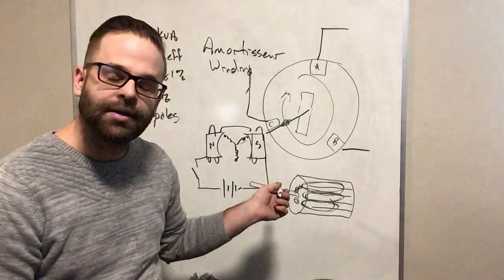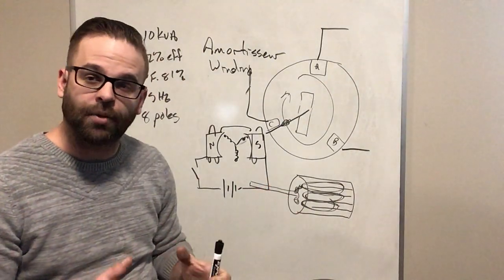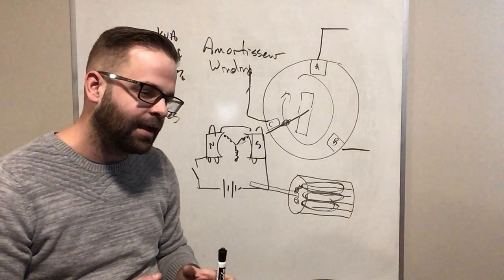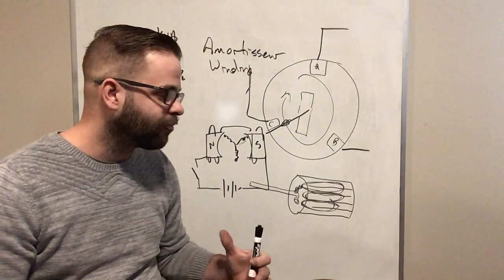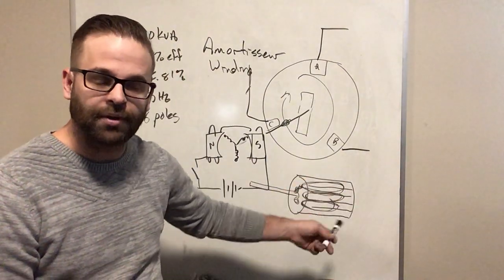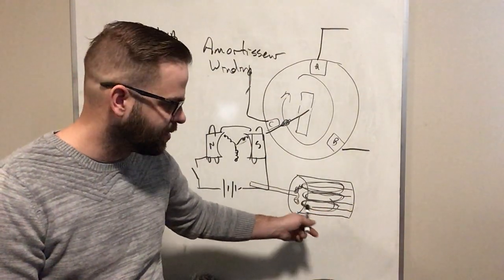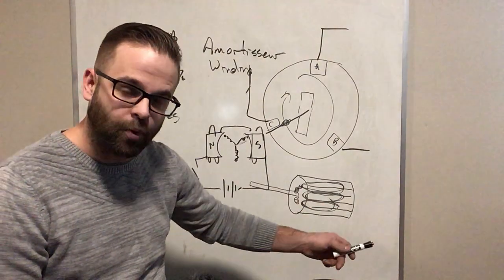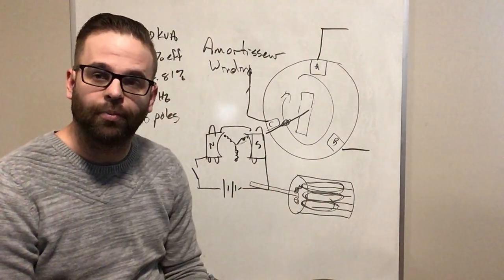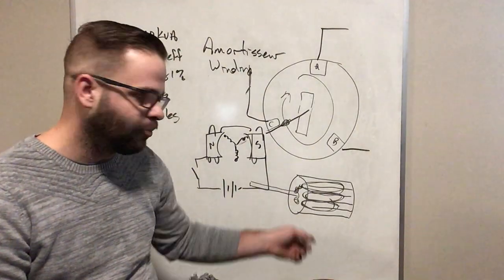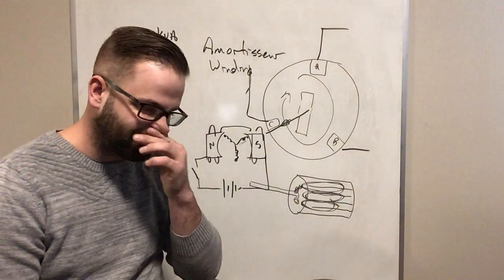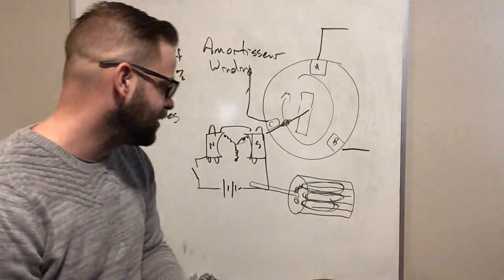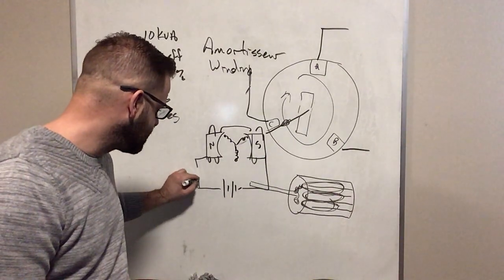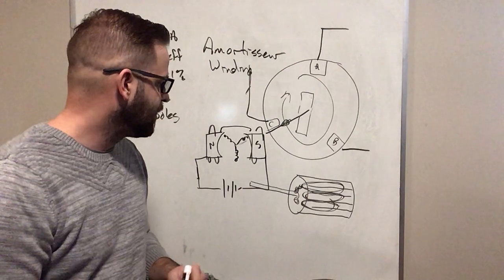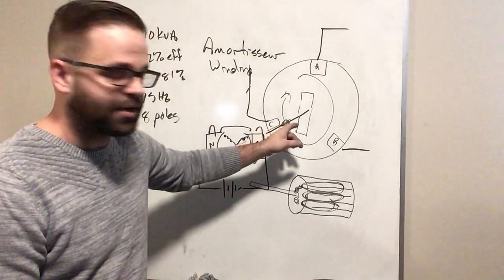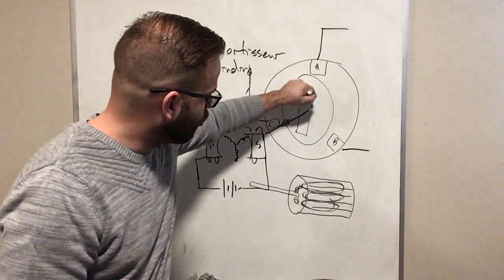Because what happens is the amortisseur winding is made of small copper, aluminum, or steel bars, and if I put it under load or leave it for a longer time, it's going to start heating up that amortisseur winding more and more, and what will end up happening is that amortisseur winding will burn out and then the motor will be screwed. So the amortisseur winding is only to get the motor up to speed. Once the motor is up to almost synchronous speed, we then close our DC excitation switch, and that ends up producing our three-phase voltage that gets rectified, comes out and gives me a north and a south.